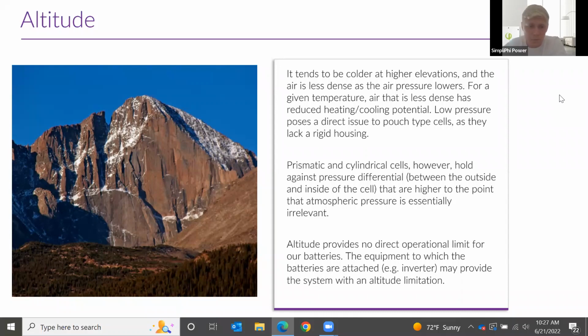You also want to keep in mind voltage at altitude. If you're going with a really high voltage device, there can be an increased potential for arcing, since the air at high elevations is actually less insulating than at low altitudes. So keeping a low voltage system is important. 48 volts is absolutely fine at high elevations, but going to a high voltage like a 600 volt residential battery is probably not a wise idea at high altitudes.